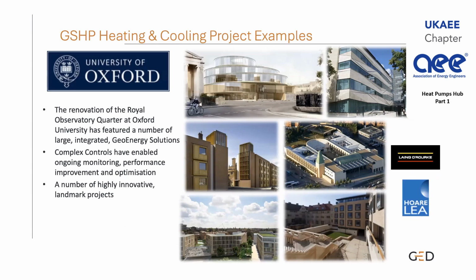So here are some ground source heating and cooling project examples. Oxford University have invested quite heavily in ground source. The Royal Observatory Quarter has a number of buildings. It started with Earth Sciences, then moved into maths, and now we have the Blavatnik School of Government, and then beyond that there is Beecroft, which is the physics laboratories. Currently at Beecroft, they are laboratories for doing world-leading physics research and development. We're getting COPs in excess of 5 there because we are managing to harness both the heating and cooling aspects of the heat pump.